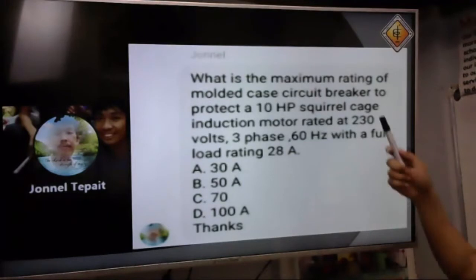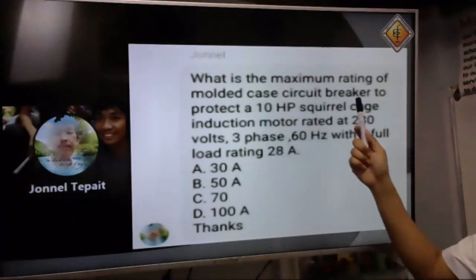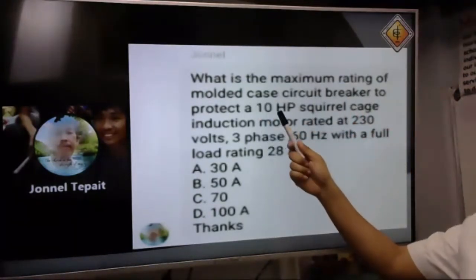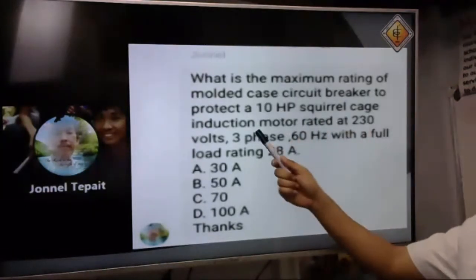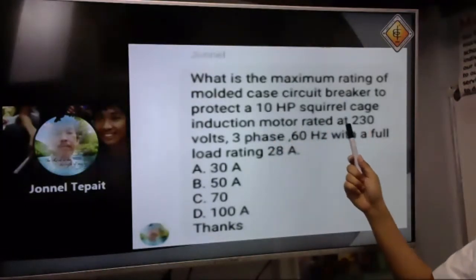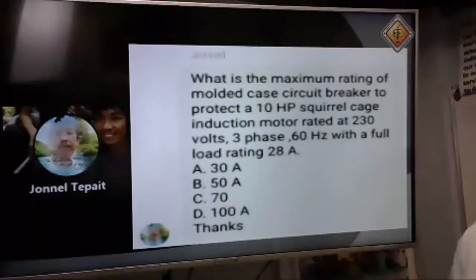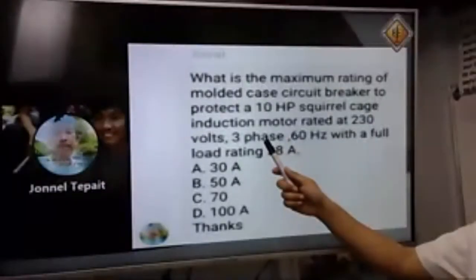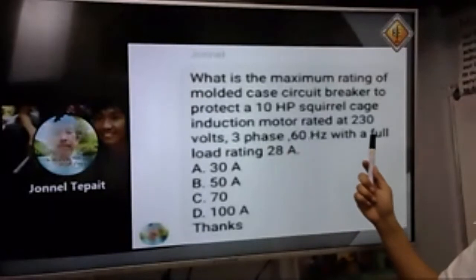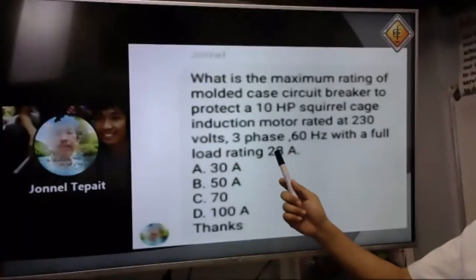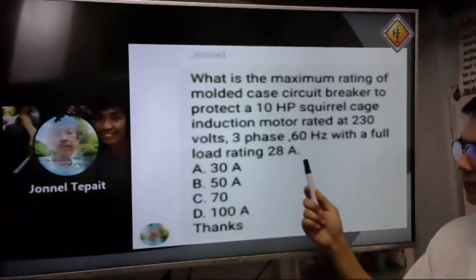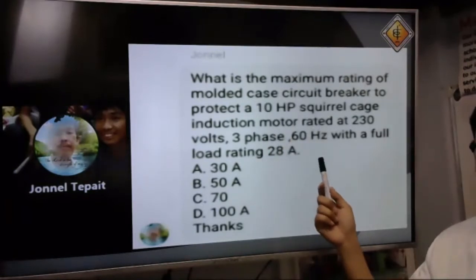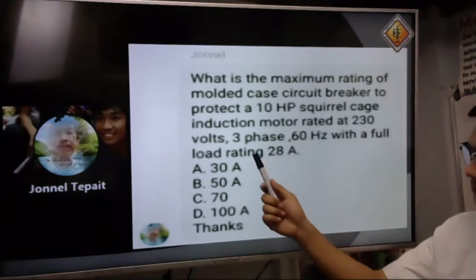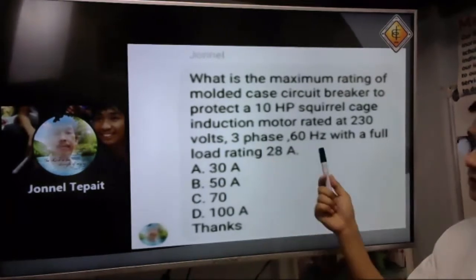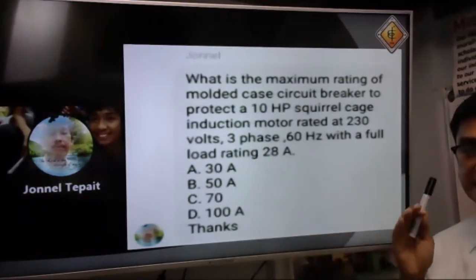What is the maximum rating of the molded case circuit breaker to protect a 10 horsepower squirrel cage induction motor rated at 230 volts, 3-phase, 60 hertz with a full load rating of 28 amperes? Okay, so we are given already the full load rating. This makes it easier.